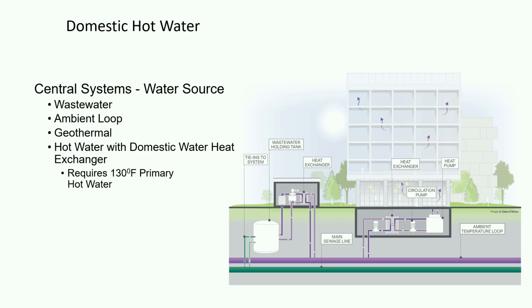Domestic hot water on these tall buildings is really important because it can be a great thermal resource now that we've got a cooling dominant load profile for all year, to pull some of that heat off of the system and reuse it as waste energy to heat your domestic hot water. And that can help balance your bore field for the long term. You've got a lot of simultaneous heating and cooling going on, so your efficiencies obviously increase dramatically for domestic hot water, okay?